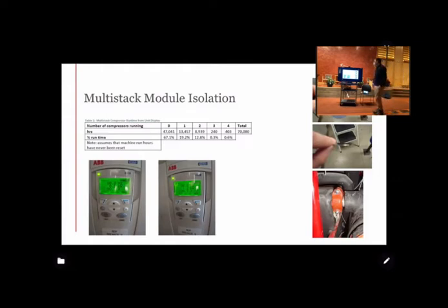And we added a drive to the pump. So we added a VFD to the geopump. And then we were using something like 9 kW, and it was running 24/7. And then we fixed an issue with a relay that was enabling the pump command on the geopump, so that when there were no compressors running, the pump would go off. And then we were running it at like half speed, and it went down to like 1.5 kW. So it was like 6 kW savings 24/7. It was something like $5,000 a year in savings. And it was something like 30% of the building energy use was just from that geopump, which is crazy. Yeah.